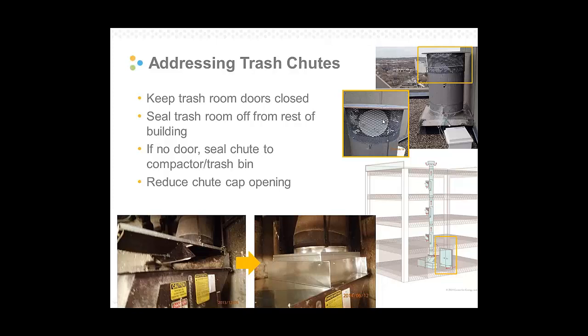And then reducing the chute cap opening. You can see on the upper right-hand corner is the cap, the rooftop termination. And you can see this cap looks like about 12 inches of open area here. You can see there's actually trash being sucked up into the bird screen here because there's so much stack flow during cold months. So reducing this area, reinstalling this cap so that it's lower so that there's just 1 or 2 inches of open area was the solution here.